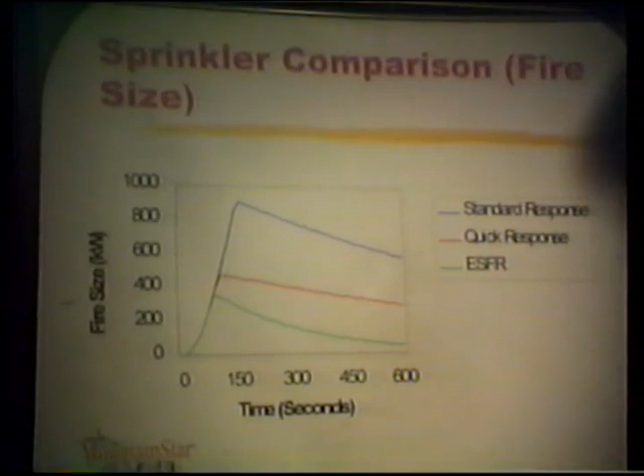Thanks, Doug. You're welcome. Okay, now what we might want to do is evaluate that, taking that same scenario, looking at the 3 different sprinkler response times, and look at the temperatures in the upper layer of that fire. And again, given the same ceiling heights, the temperatures are going to be higher when we use standard sprinklers versus quick response and possibly with the ESFR.